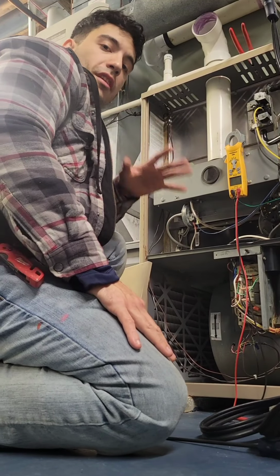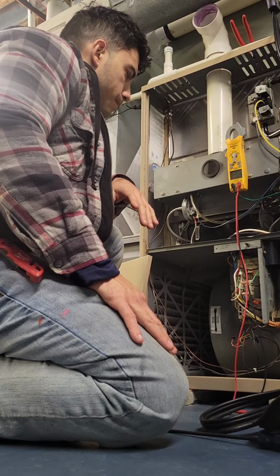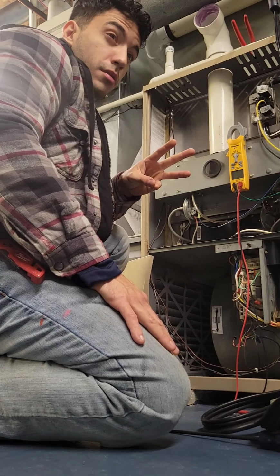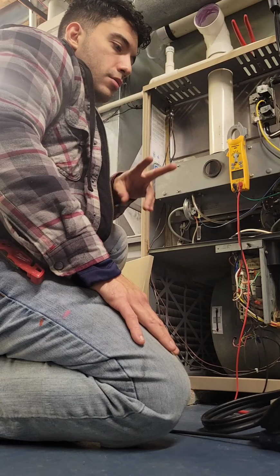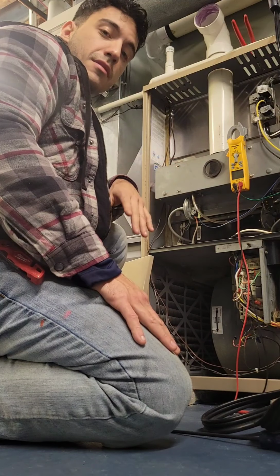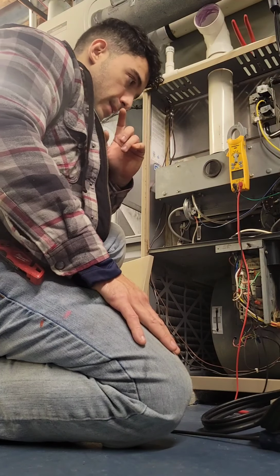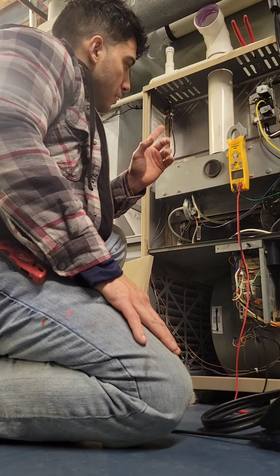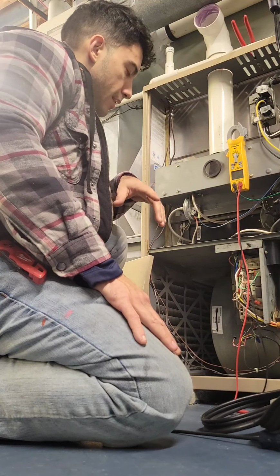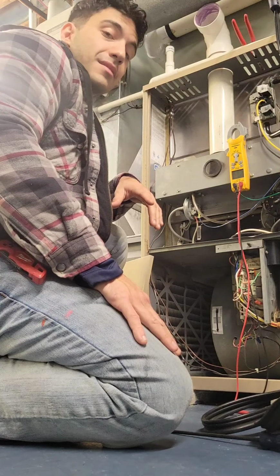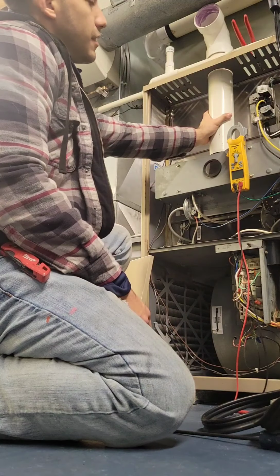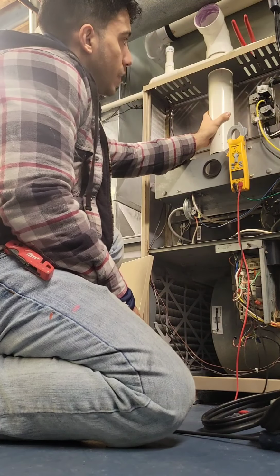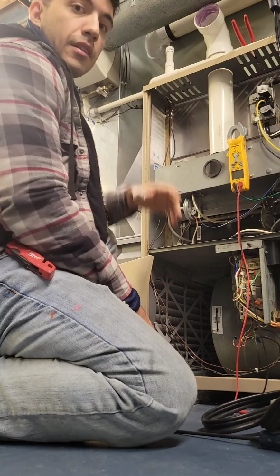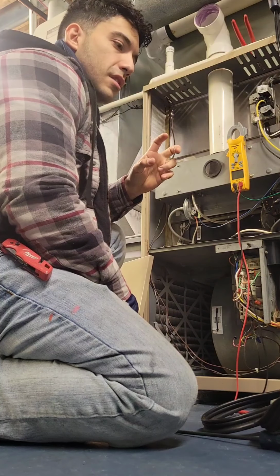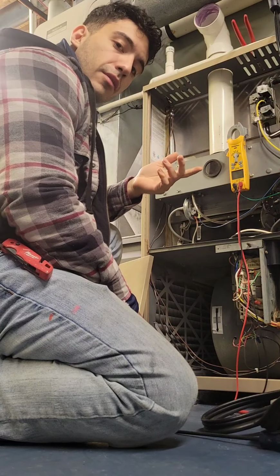So today, nothing crazy. We have like 3 calls to get done. Two are maintenances on systems. One's natural gas, one's propane. This particular system that we're checking out today is natural gas. So you can see it's a 90% furnace, and you can usually tell that it's 90% or high efficiency if it has white PVC venting to the outside.